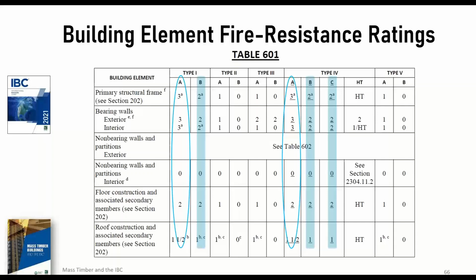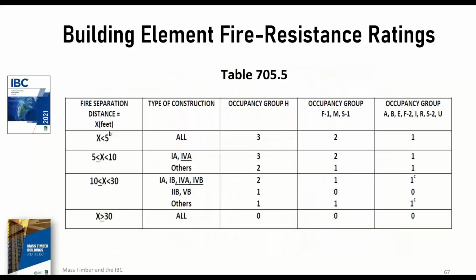And it's worthwhile to note that we're not really covering on this topic all the types of construction. Type 4A, B, and C are required to be protected by NFPA 13 sprinkler systems. So all concealed spaces, closets, bathrooms, dwelling spaces, hallways, dead-end hallways are going to be mandated to be protected by NFPA 13 type sprinkler systems.